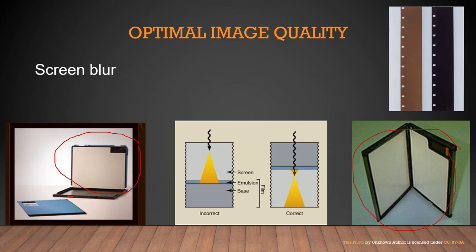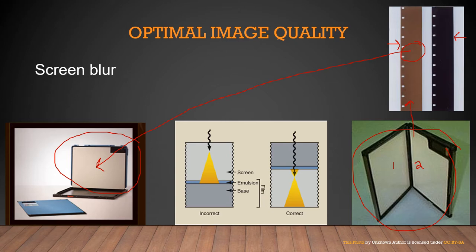If I'm looking at the film, the real bright and shiny part does not have the emulsion. The emulsion actually dulls the film. So the dull part would be facing the intensifying screen, and that's going to reduce screen blur. If I had a double screen cassette, I would have to have emulsion on both sides of my film. We were using the single cassette with only one intensifying screen even when I first started in x-ray school.